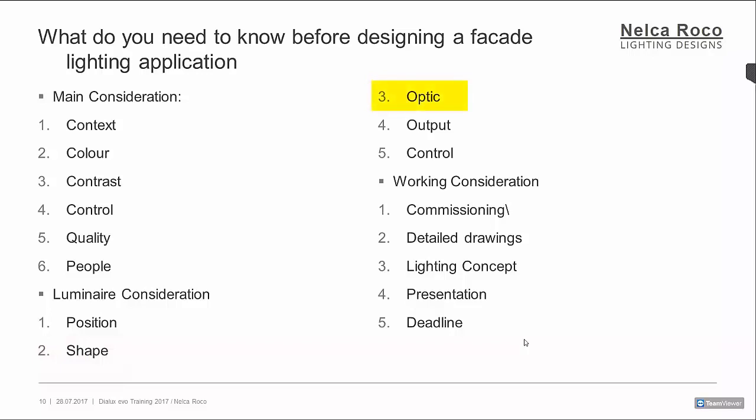Optics — there are different kinds of optics. For floodlights, there's wide beam, narrow beam, and different optics give different effects on your facade. For example, if you want even illumination or wall washing, you don't need a narrow optic. You want a wide beam or a linear flood to achieve wall washing or even illumination on the facade.